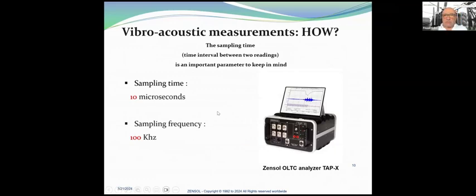So for vibroacoustic measurement, how do we do this? The sampling time is the time interval between two readings, and it is an important parameter to keep in mind. For vibroacoustic, we use 10 microseconds, and I think it's the minimum that we must have. Any value above this is not good. This is a sampling frequency of 100 kilohertz. Here you can see the TAP-X that we use for this recording.